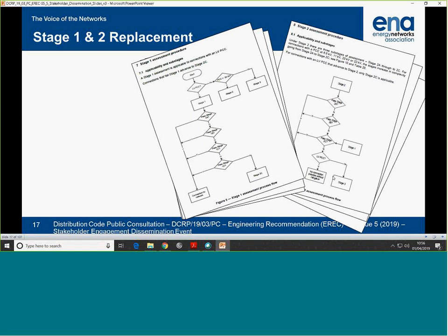So stages 1 and 2 have been completely rewritten. The document concerning stages 1 and 2 runs to 99 pages. But in doing the change, we've retained some of the principles involved. The increasing complexity of assessment fits with the need to cover the volume of connections, in proportion to the risk that they present. That's retained. Use of standards to simplify the assessment method, which manufacturers have to comply with anyway, I'll cover later. And the idea of a maximum harmonic impedance curve that the working impedance sits under has also been retained.